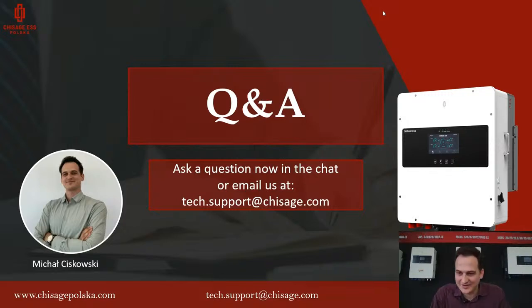Okay. So the question is how much load we can connect to EPS load. For the EPS load, we can connect a maximum of around 18 kilowatts. So it's 26 amps. We can connect 26 amps to the EPS load in on-grid mode, of course, because the inverter will take this from the grid if you need. But for off-grid mode, it will go with inverter power. So basically, if we want to support all the EPS load all the time, it can be maximum inverter power. So for Mars 10 it will be 10 kilowatts for EPS load.